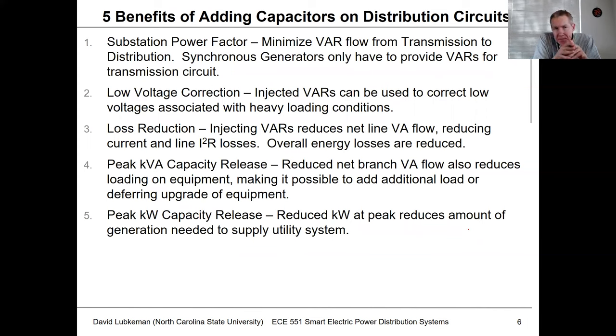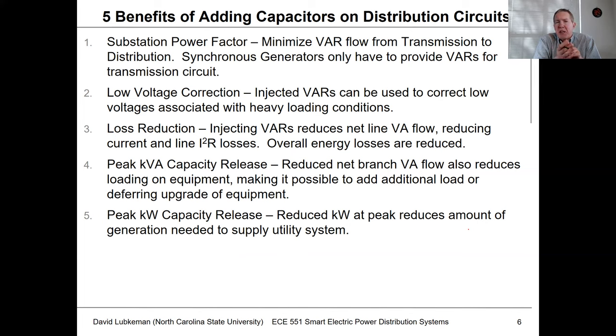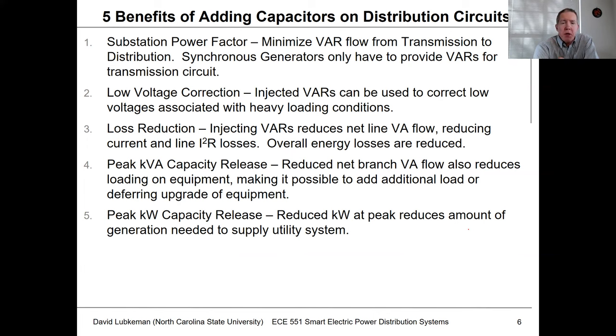There are five basic benefits associated with placing capacitors on a circuit — important to know when evaluating any investment. The first benefit is improving the substation power factor by minimizing VAR flow. If we have load that consumes reactive power, that reactive power has to come from generation or capacitors somewhere in the transmission system.